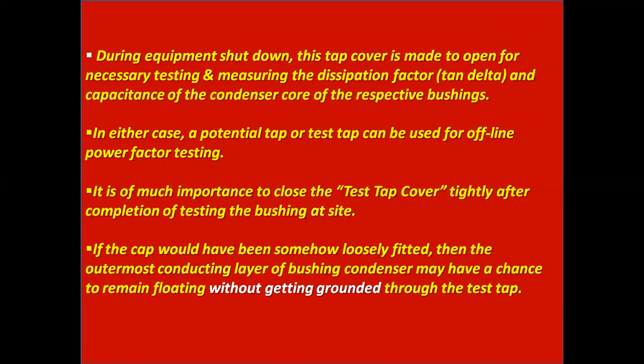During equipment shutdown, this tap cover is opened for the necessary testing and measuring of the dissipation factor, that is tan delta, and capacitance of the condenser core of the respective bushings. In either case, a potential tap or test tap can be used for offline power factor testing. It is of much importance to close the test tap cover tightly after completion of testing the bushing at site.